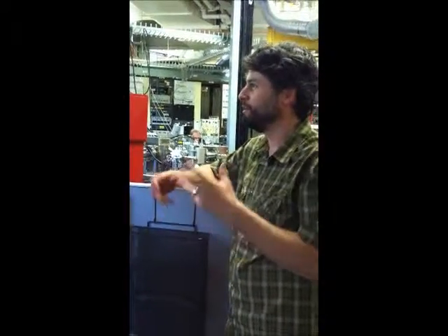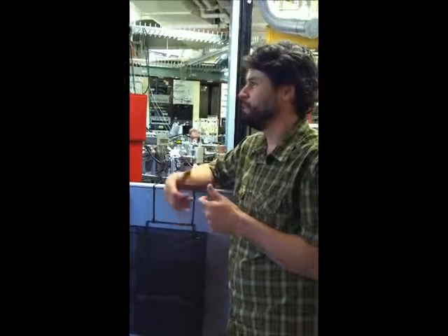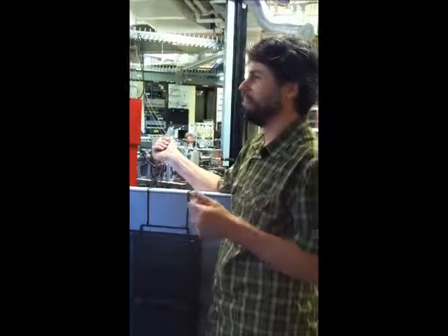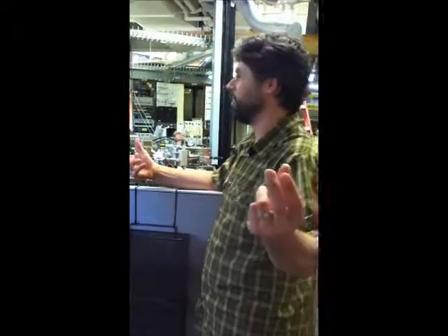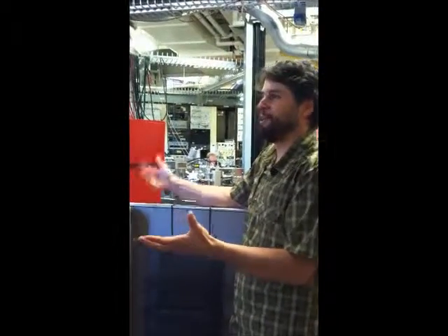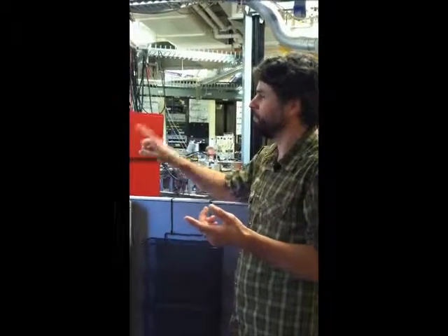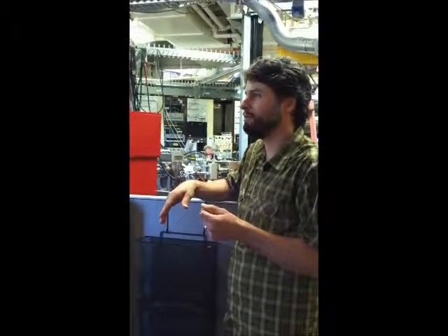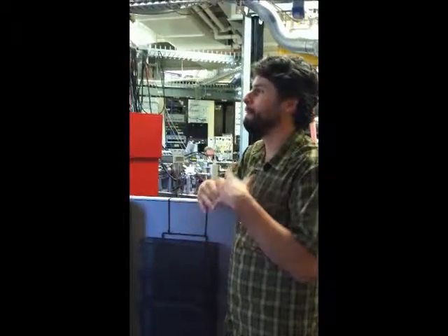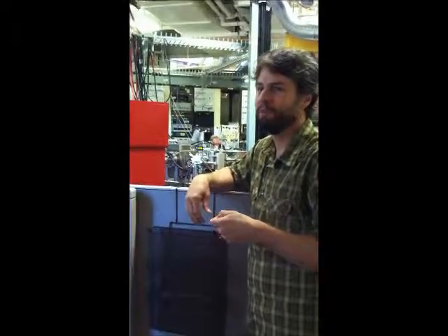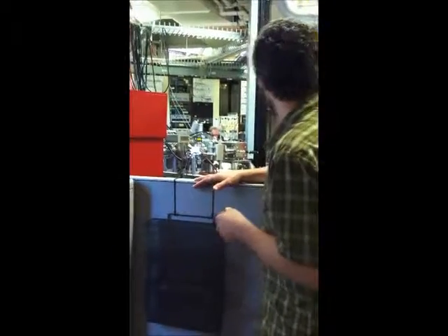Building the experimental chamber that goes on the end, that's really where the beamline scientists can do their thing and know how to build these manipulators and load samples. And if you think about it, there's 10 to the minus 10, maybe a little worse than that, vacuum in there. How do you actually take a sample from out here in the air and load it into that vacuum while maintaining the vacuum? The vacuum levels in our machines are good enough that if you were just to put a fingerprint on the inside of our machine, you would degrade our vacuum to the point where we would have to shut down for a couple weeks, clean it out, bake it, which means cook it to get all the stuff off the inside to get back to a good enough vacuum. So maintaining vacuum is huge here.